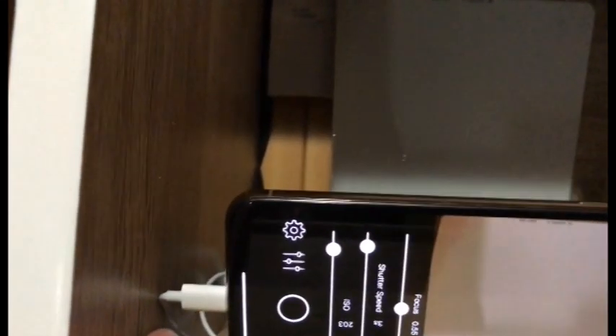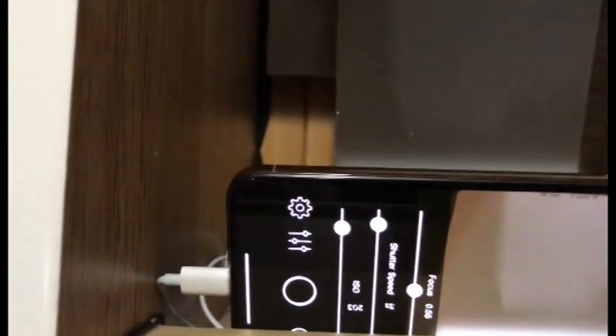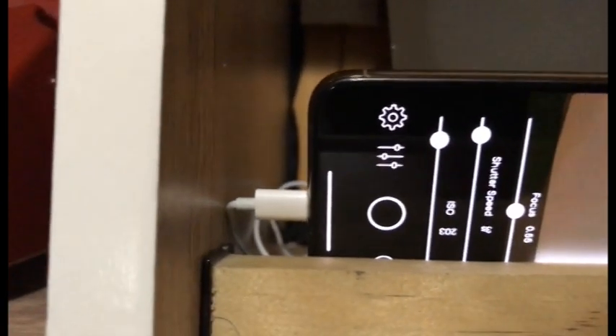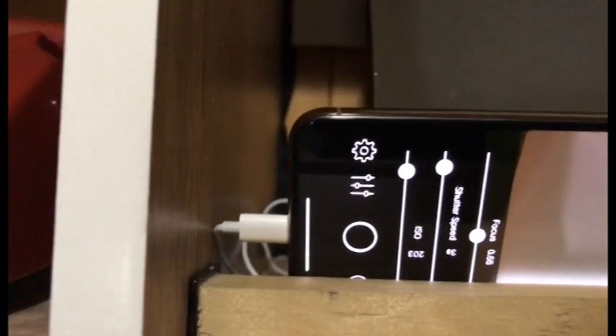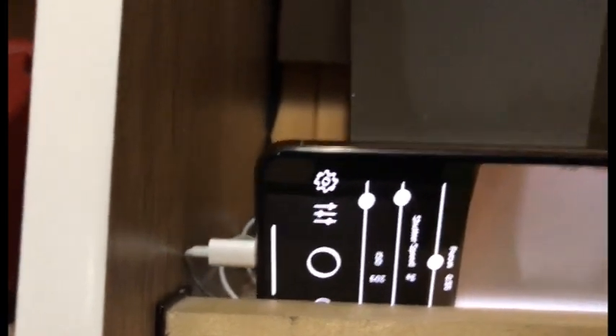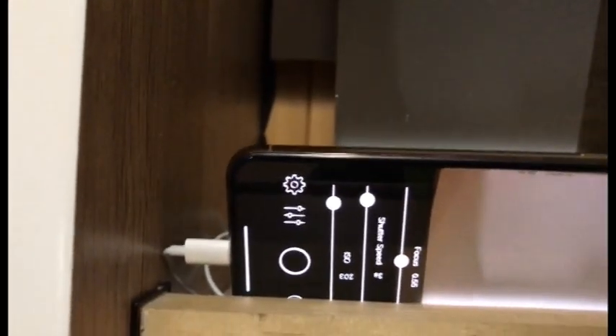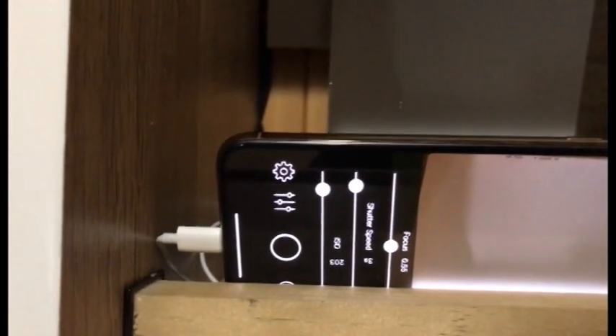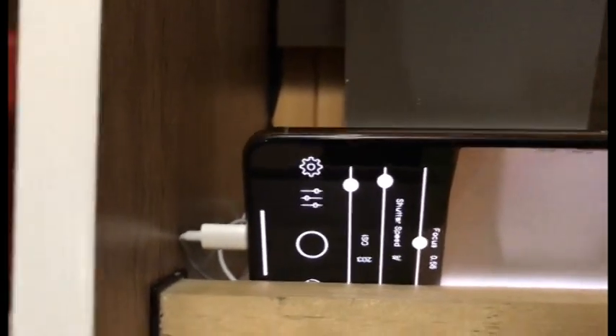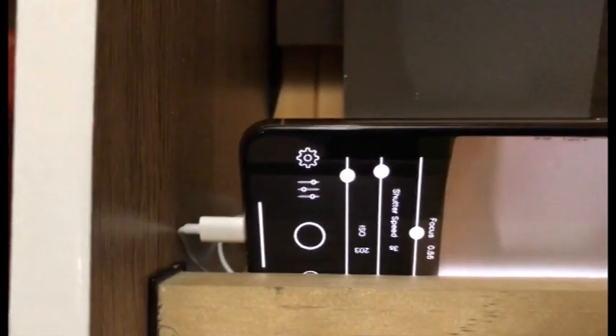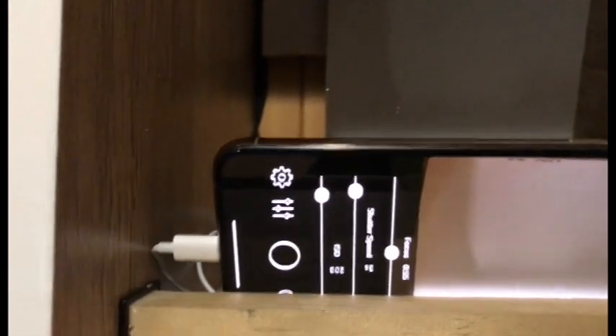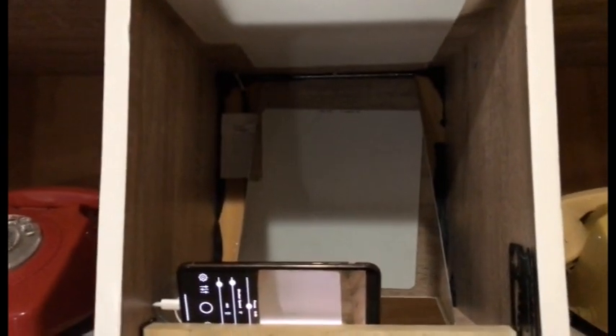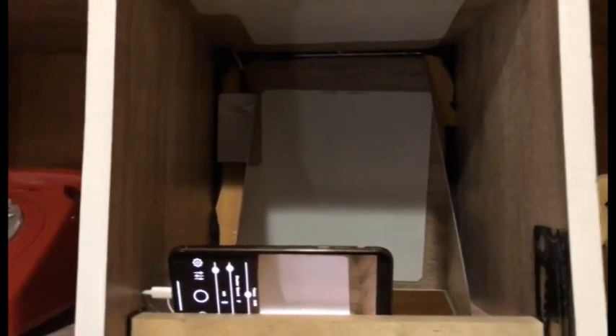Here you'll see a lightning port that's not for charging. That is a modified headphone cable. So on the iPhone you can use the volume up and volume down button to take a snapshot, and I have modified that and connected it to the PLC. So when the X-ray tube begins X-raying, it will automatically trigger the exposure.